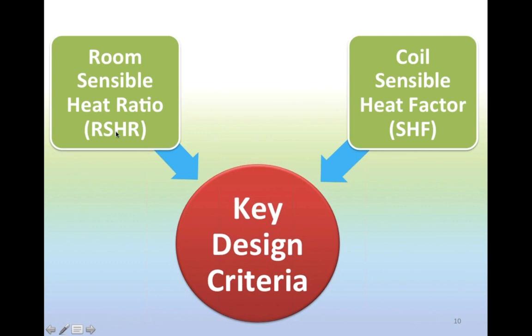The first one is the room sensible heat ratio, which, as we would know as designers, is the total estimation of the cooling loads. All of us are aware that it consists of the sensible cooling load due to the conduction gain that comes from the opaque surfaces, the wall, the windows, the solar heat gain, the lights, the other equipment heat, and so on and so forth. And then we have the latent load that primarily comes from the occupants. That's in terms of the room sensible heat ratio.